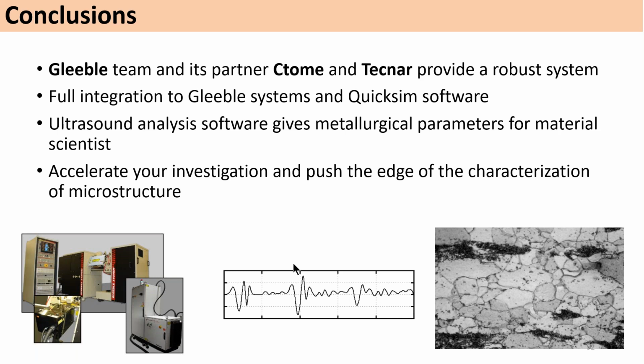Yeah, for sure. In terms of the minimum thickness, I would say below 1 millimeter it starts to be difficult to extract the longitudinal pulse. As the sample becomes thinner and thinner, the whole sample starts to vibrate. It's like a plate wave, and so we no longer see the longitudinal pulse unless we apply very strong filtering of the low frequencies.